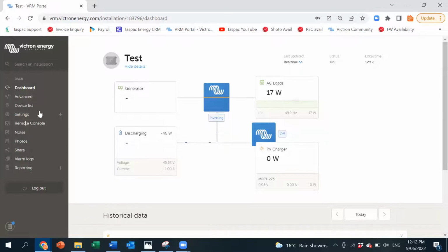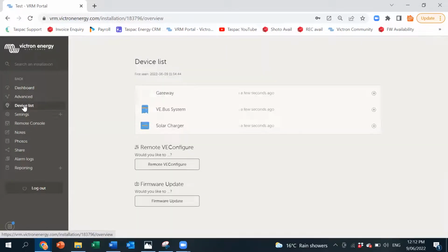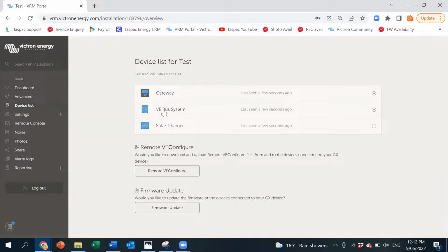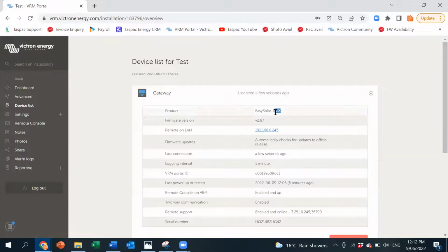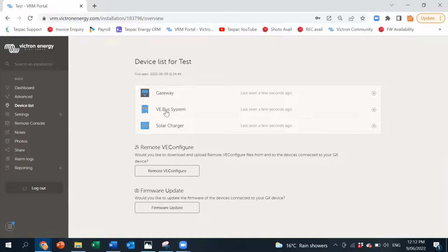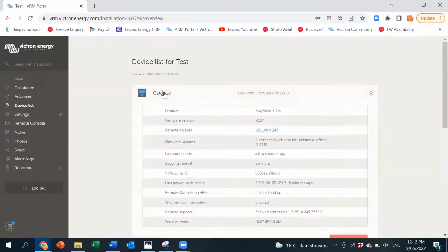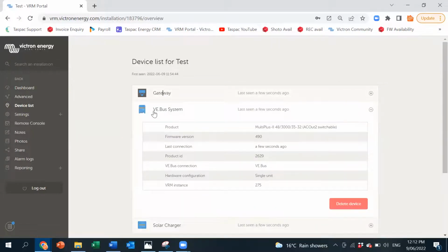Now we're going to go into the device list, and you will see the 3 devices that are built into the Easysolar. You've got a gateway, which is your GX device, which we've just programmed, by the way. You've got a VE bus system, which is actually the inverter, and you'll see here it's a multi-plus 248 3000, and it shows you a few details on that.